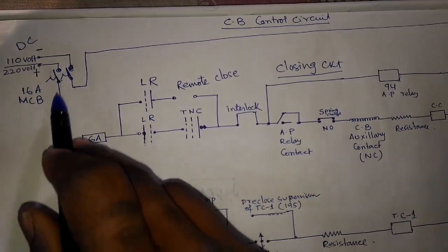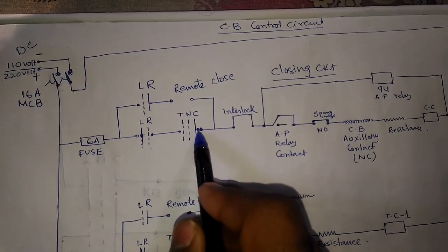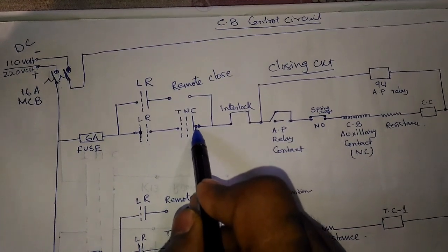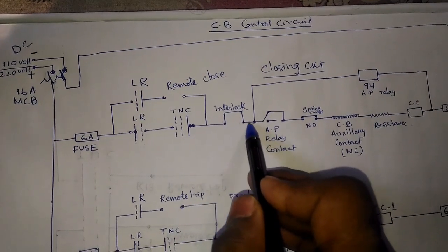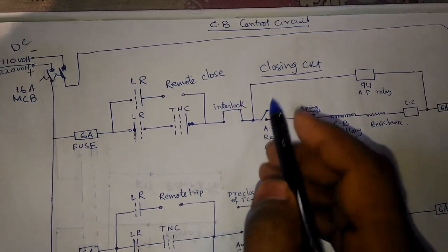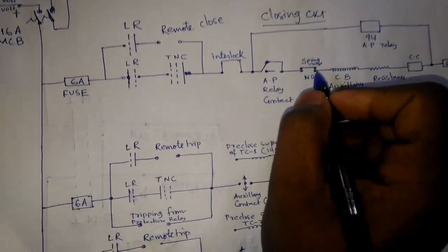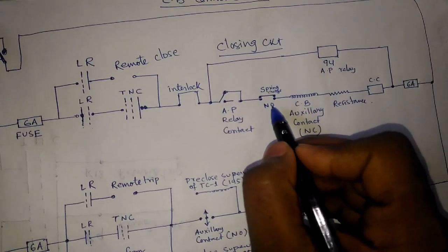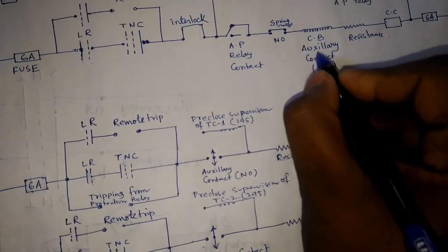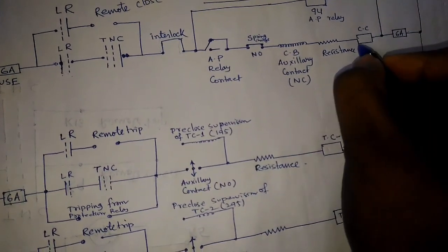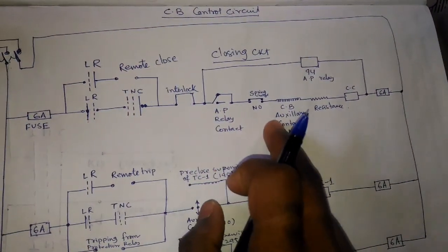The positive DC voltage is coming through the fuse and the LR switch, and we are operating the closing command. The voltage passes through the interlock, then through the anti-pumping relay NC contact. If the circuit breaker spring is already charged, the power passes through this NO contact, then through the circuit breaker auxiliary contact — also NC — then through the resistance and the closing coil, completing the circuit through the negative terminal. So the closing command is provided to the circuit breaker.